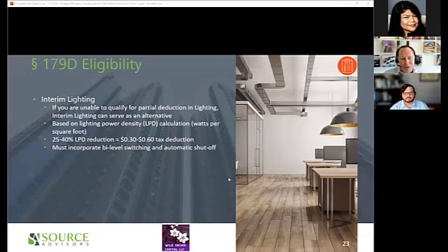So it's based on the lighting power density calculation, which is in watts per square foot. And a 25 to 40% lighting power density reduction equals 30 cents to 60 cents of tax deduction. To qualify for this, the property must incorporate things like bi-level switching and automatic shutoff in their lighting. I looked at a property earlier this week actually, looking for exactly this, and unfortunately they did not have that bi-level switching or automatic shutoff, so they were not going to qualify for the interim lighting.